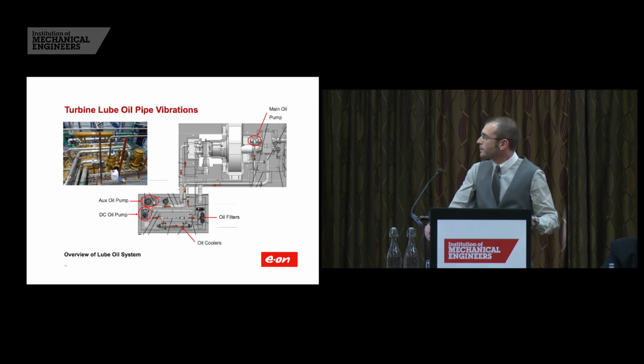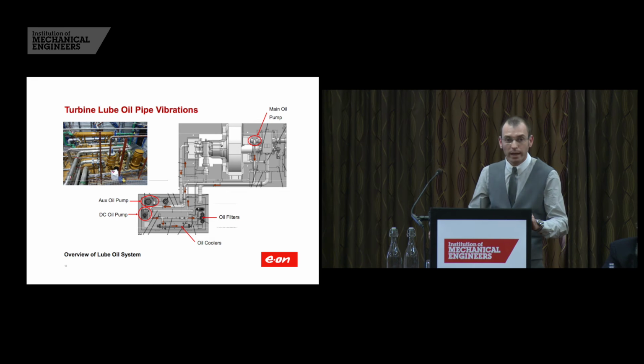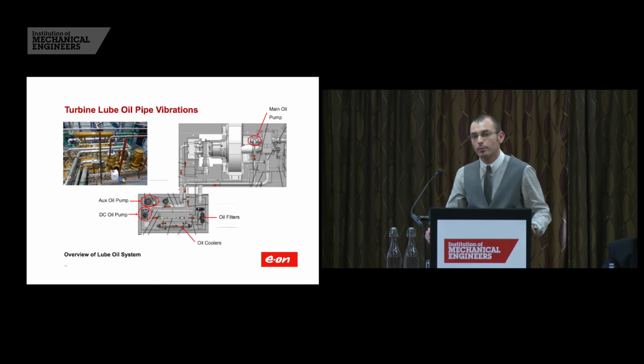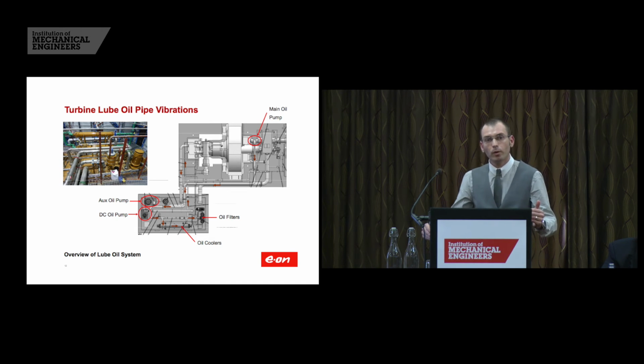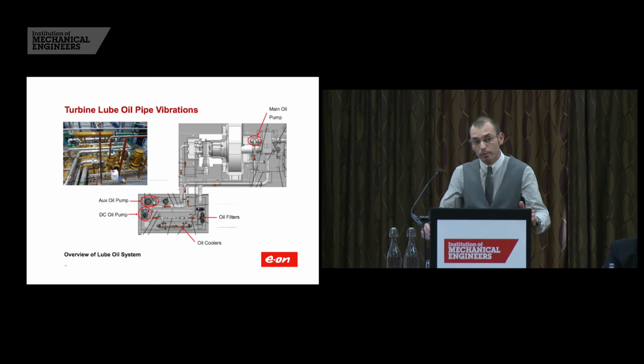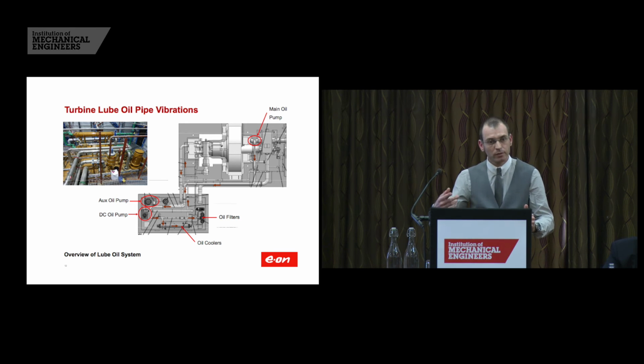Moving on to commissioning, one of the first items, when we ran up, we had a slight challenge with the lube oil system. I'd like to explain first of all how this system works. We have a main shaft-driven oil pump, an auxiliary oil pump, and a DC backup emergency pump. On first startup, both the auxiliary oil pump and main shaft-driven oil pump are running in parallel. When the machine reaches 95% speed, the auxiliary oil pump cuts out, and the shaft-driven oil pump should provide enough flow for the entire system.